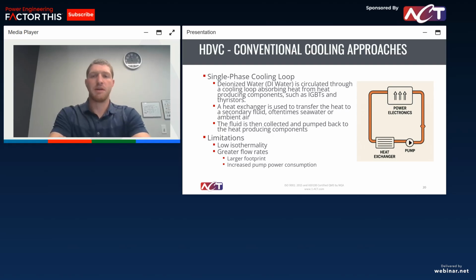The other primary conventional cooling approach is a single phase cooling loop. This will typically have deionized water or another water-based coolant circulating through a loop. It'll typically go through your power electronics, whether that's in a cold plate or immersion cooled, and be taking away heat from there and absorbing that, being pumped back to a heat exchanger. That heat exchanger, depending on the application, is often either a liquid to air heat exchanger, like a tube and fin heat exchanger, where you're rejecting that to ambient air, or oftentimes if you're a more seaborne application, you can reject that to seawater or another liquid loop. And then that fluid is pumped back into the heat producing components.